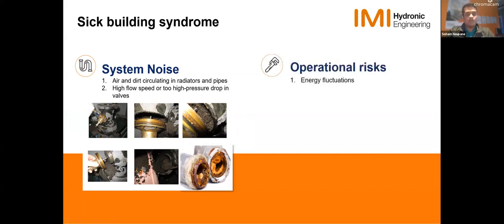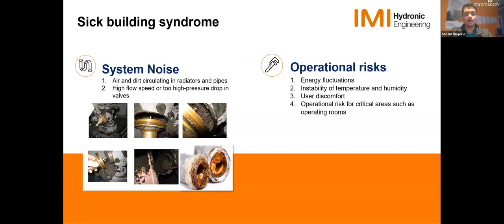And then, we go further, there are operational risks. We're going to see a lot of energy fluctuations in a sick building. You're going to see instability of temperature and humidity. So that's going to cause user discomfort. And, at the end, your system would basically not operate like it should, and you're going to have the operational risk. And especially when it comes to critical applications, that's a major concern.